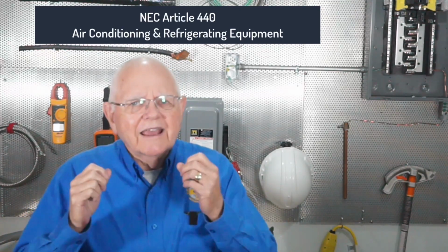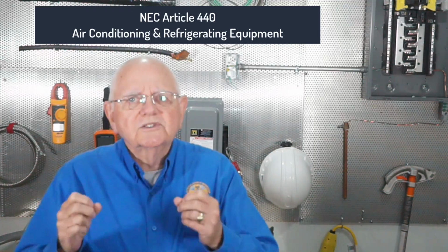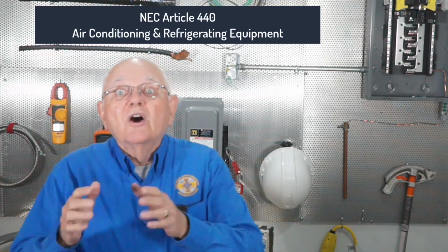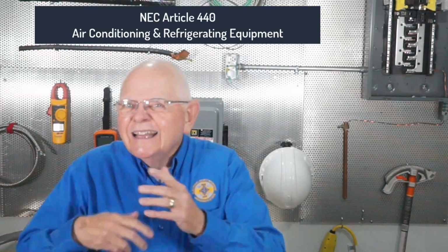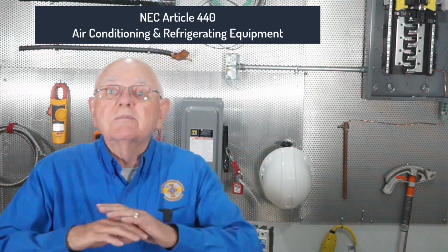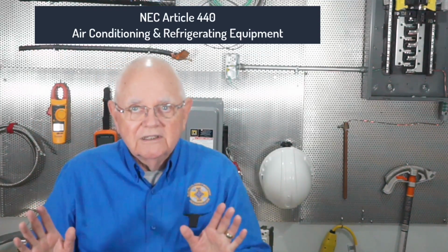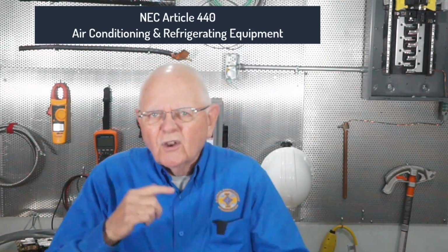If you think about it, air conditioning and refrigerating equipment, we're talking about the compressor and some fans, so we're talking about electric motors. However, Article 440 is going to make some changes for us. So remember, the whole code applies, right? The NEC applies to everything in Chapter 4, and Article 440 is in Chapter 4, Equipment for General Use. So let's see what we can pull out.